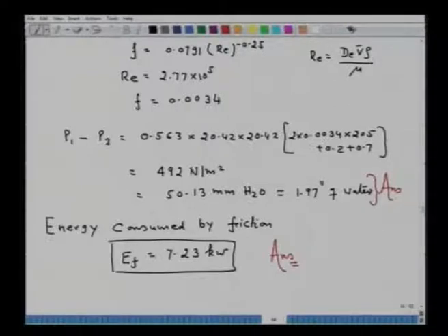Now, next we have to calculate for a certain given pressure difference. So, we have to find out what is the minimum cross sectional dimension of the flue. Now, the same equation will be valid. Say we have P2 minus P1 upon rho, that is equal to V bar square by 2, F L upon dE plus 0.2 plus 0.5.